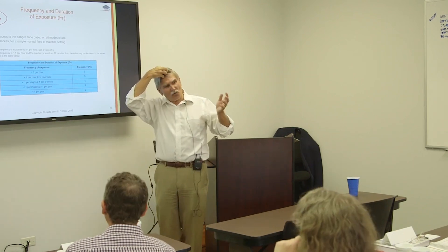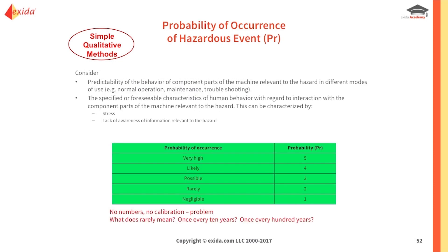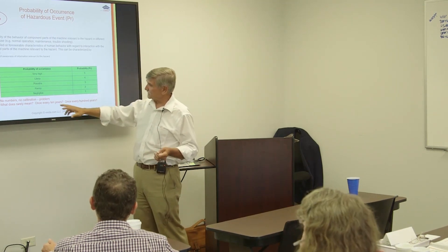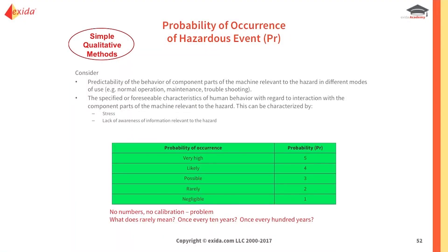For frequency — how often is a worker exposed — less than once per year gets two points, and it goes up to five points. That's occupancy in effect. For probability of occurrence, the categories are words like 'negligible' and 'rarely possible.' Whatever the words mean to individual people, you pick a number and get some points. The problem is there's no calibration. What does 'rarely' mean — once every ten years or once every hundred years? Your group must decide that up front, typically in a corporate procedure.